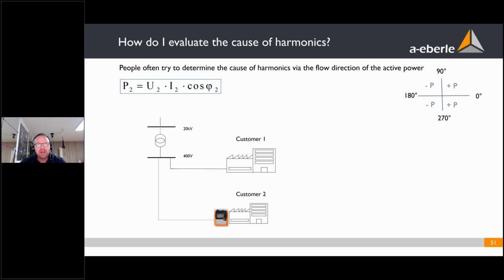So now we go to a real case. With a public grid, in this public low voltage grid, we have a problem of the 7th harmonic. The 7th harmonic is too high. So we install a power quality analyzer at the customer two, which is a big production company. We measure here the current of the 7th harmonic. The 7th harmonic produces a voltage drop over the line and the transformer impedance of 0.57 volt.